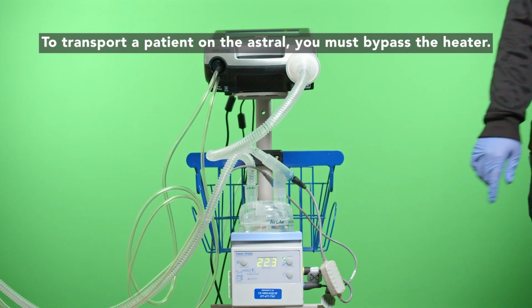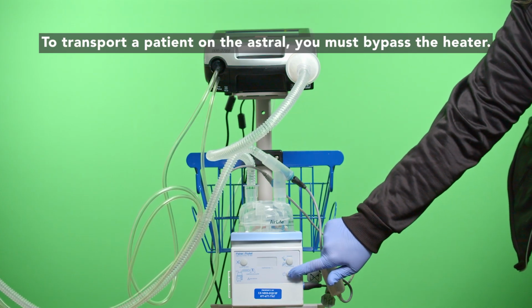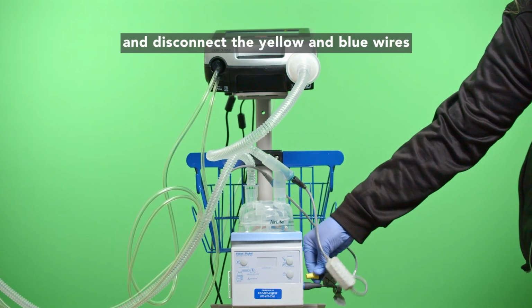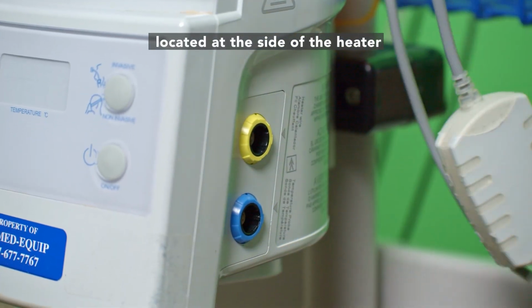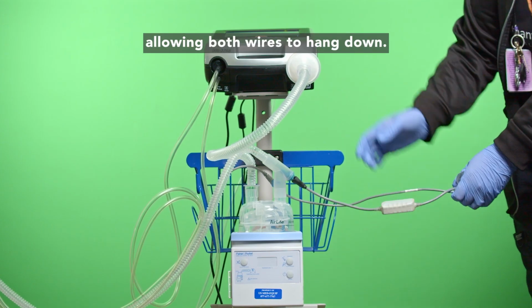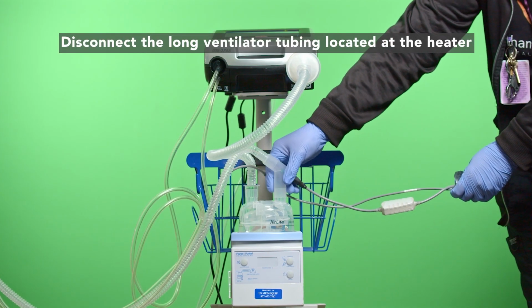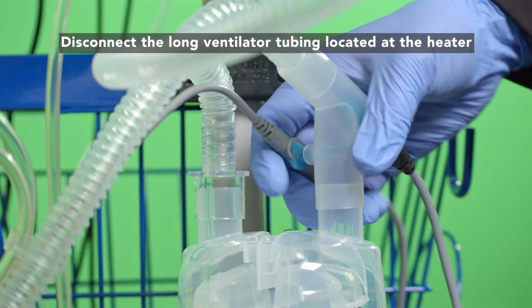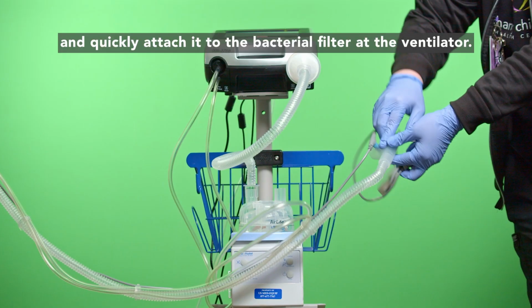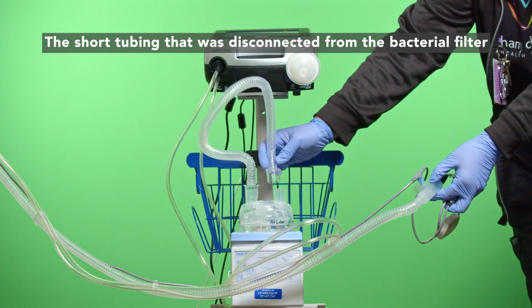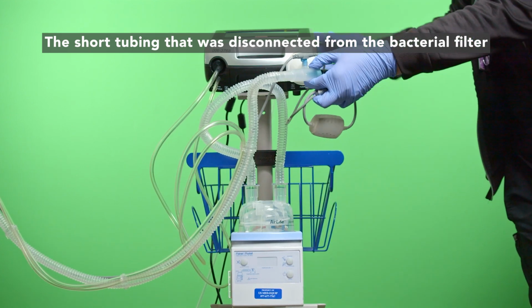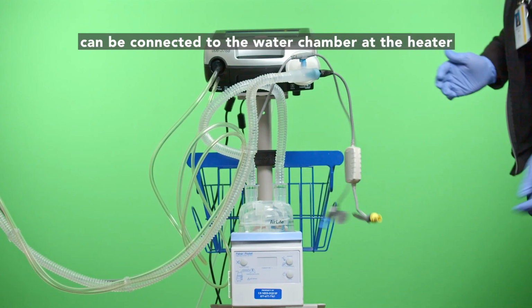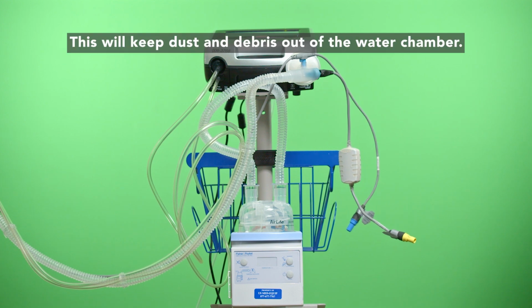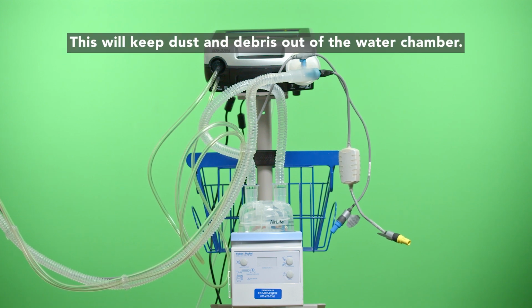To transport a patient on the Astral, you must bypass the heater. To do so, turn the heater off and disconnect the yellow and blue wires located at the side of the heater, allowing both wires to hang down. Disconnect the long ventilator tubing located at the heater and quickly attach it to the bacterial filter at the ventilator. The short tubing that was disconnected from the bacterial filter can be connected to the water chamber at the heater, creating a loop. This will keep dust and debris out of the water chamber.